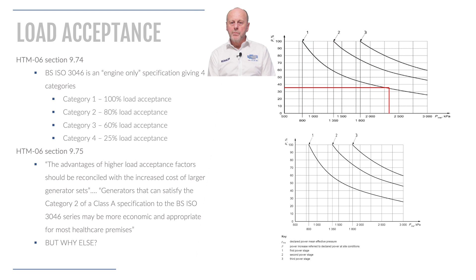So on this slide, we begin by looking at load acceptance of a diesel generating set, which is based on the ISO standard section 5. Here, the standard defines the load acceptance level on the basis of the brake mean effective pressure of the engine, not a specific percentage, which is what is required within the HTM. This allows for variations between engines and manufacturers in the ISO standard. Also in the ISO standard, performance isn't aligned with HTM06. Although 60% load acceptance at first step of a prime rated generating set is typically accepted as an industry norm.